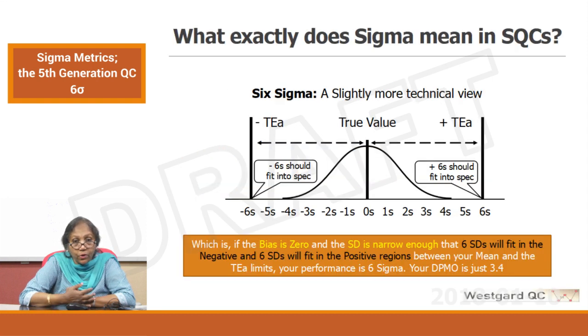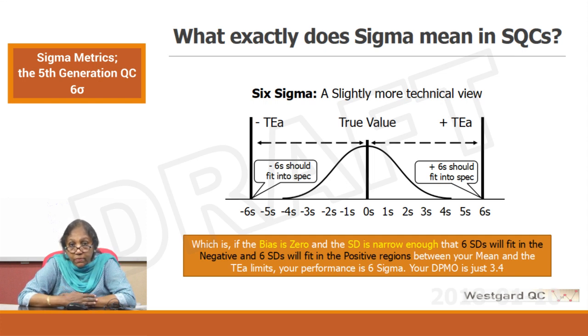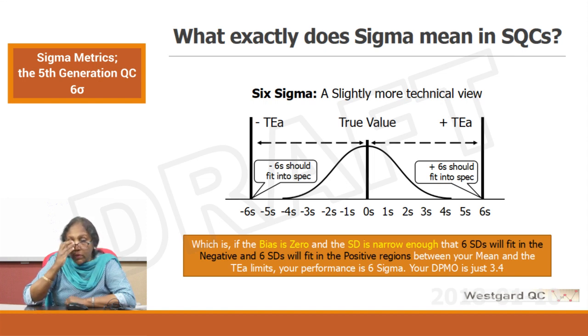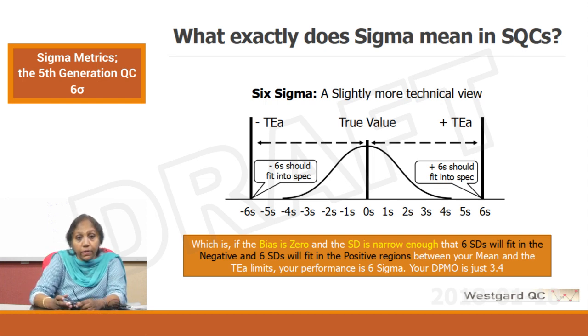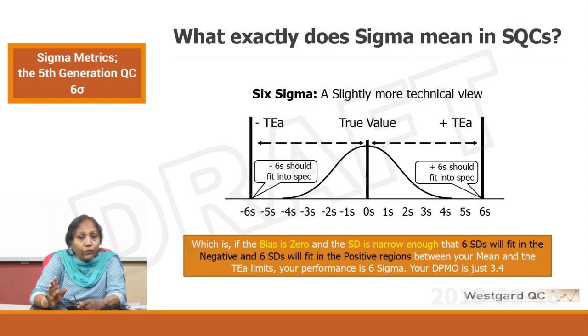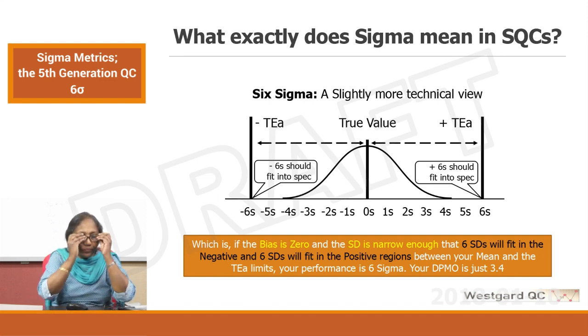Now we are going to talk about the technicalities of finding out the sigma in your laboratory for every analyte. Understand it is not a laboratory which has a sigma — it is an analyte. And even if you have got two clinical decision levels, you are running quality controls at a high level and low level. Sigma has to be understood for both these levels so that you understand the performance of that analyte at whatever clinical decision level you can calculate that for.